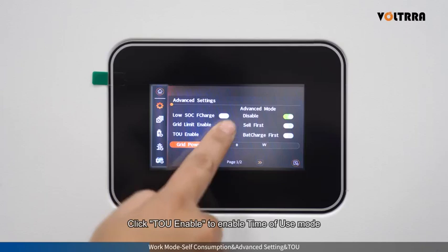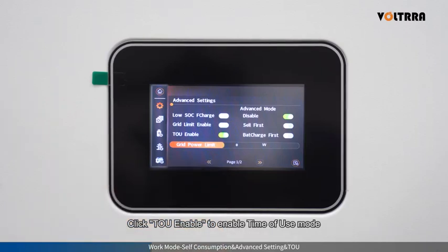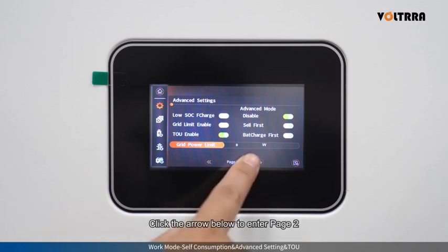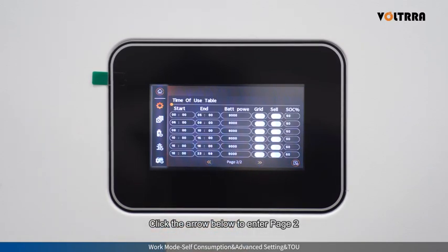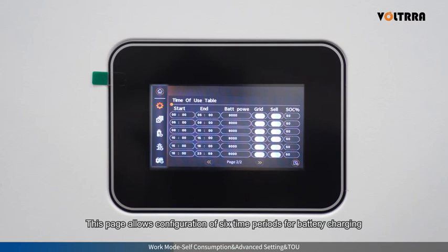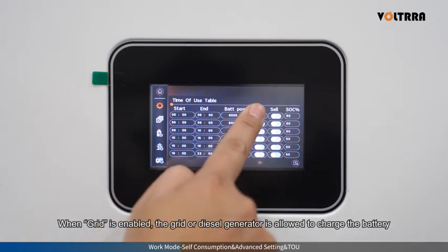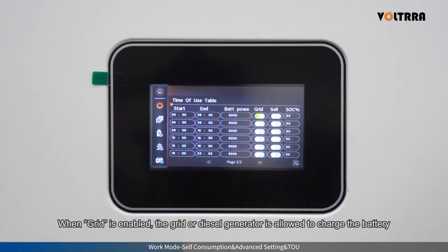Click TOU Enable to enable time of use mode. Under self-use mode, the system can charge the battery using the grid or diesel generator, storing a certain amount of energy in the battery. Click the arrow below to enter page 2, the TOU settings interface. This page allows configuration of 6 time periods for battery charging. Within the configured time periods, choose either grid or diesel generator to charge the battery.